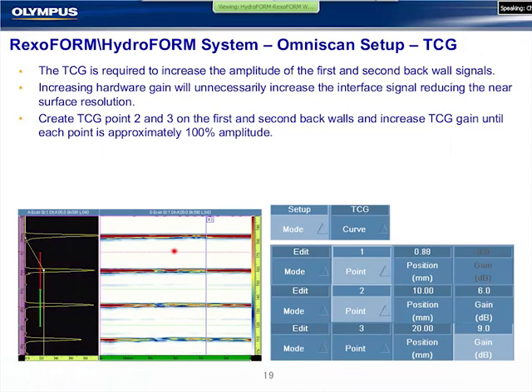So the next thing we'll do is the TCG. Now, there's no code requirement for sensitivity calibration or time-corrected gain, but what using the TCG does is allow us to increase the amplitude of the backwall signals without increasing the amplitude of the surface interface signal. When we talk about near surface resolution, and we'll see it a little better on some larger displays shortly, the larger this interface signal is, the more difficult it is for us to detect and measure a reading in that area. So I can move this gate very close to this as long as it's small. So using the TCG allows us to boost these signals without boosting this one.